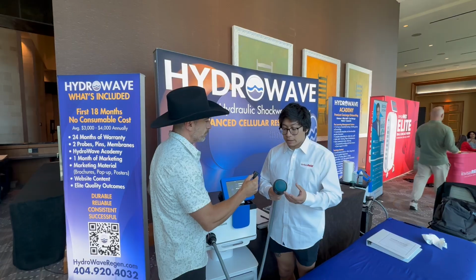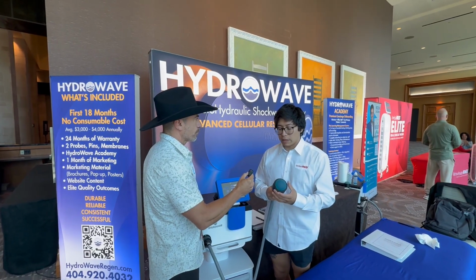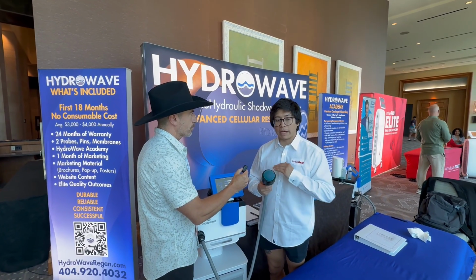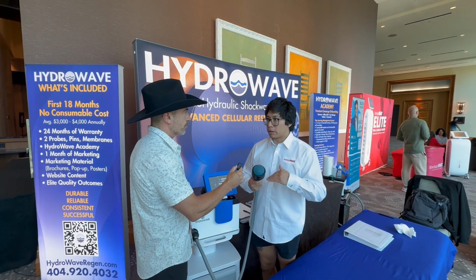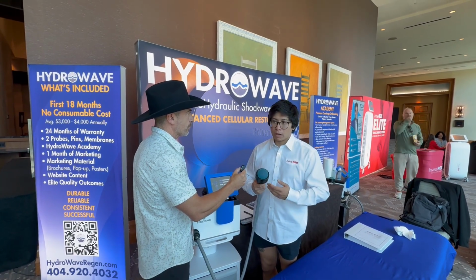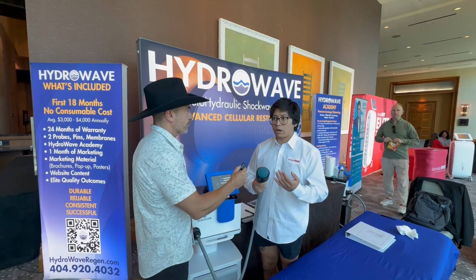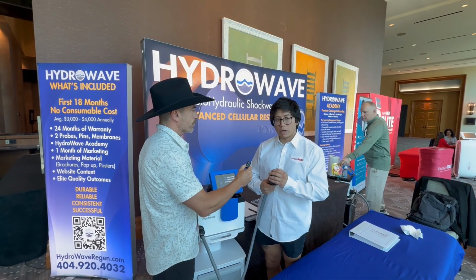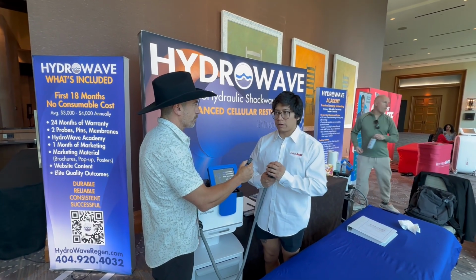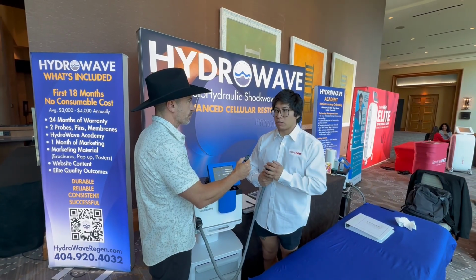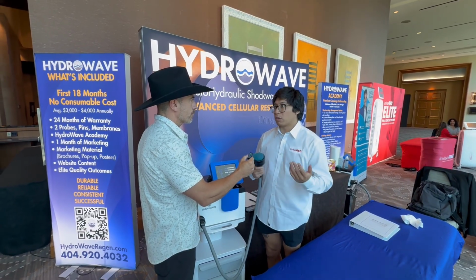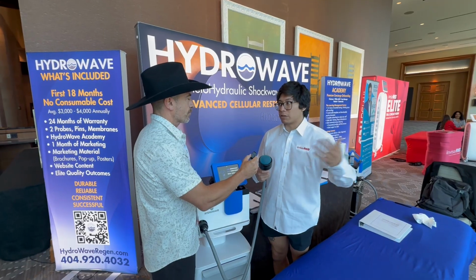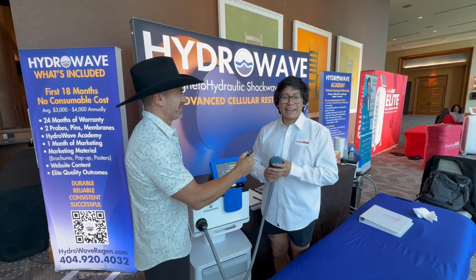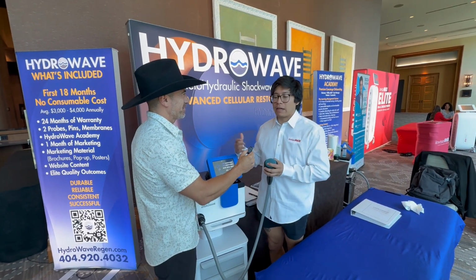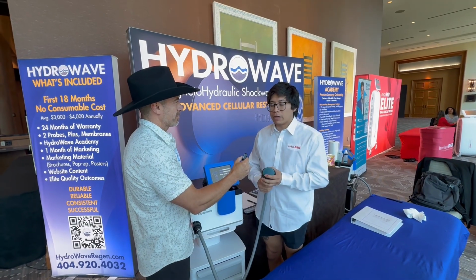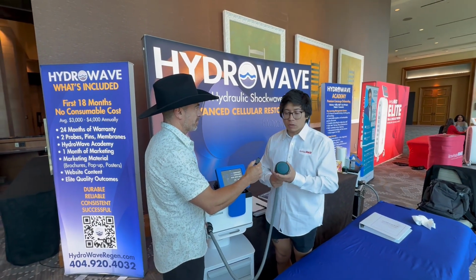If you notice there's any leakage coming through, that would mean the diaphragm itself from the electromagnet has been broken. If you're running it at really high energy levels with barely any water, there isn't that dampener, the water, to help the diaphragm stay intact. So then you would blow it out just like you would with a normal speaker if you were to turn up the bass and run your speakers at full blast. So if you're not running it at full blast every single time with no water, then your membrane, your head, and everything would still be intact.